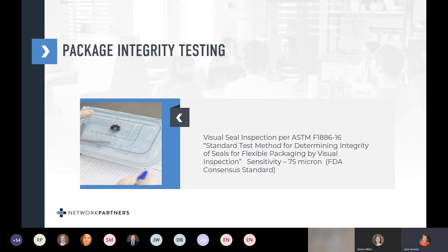Again, sterility can't easily be measured. Therefore, package designs and processes must be validated and controlled. In a sense, the performance testing we discussed is a conditioning event, and the integrity test methods employed to determine acceptance criteria are the true tests.